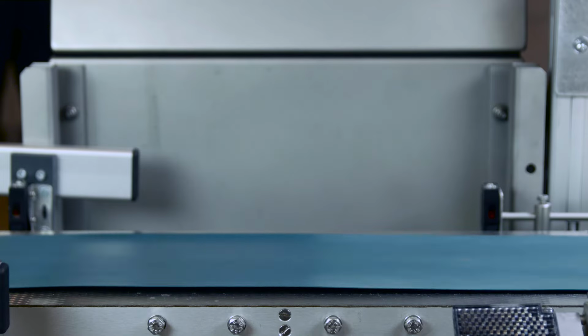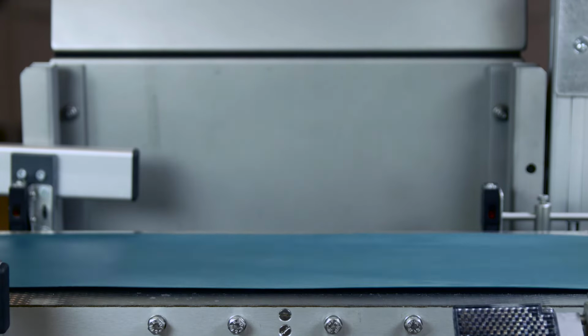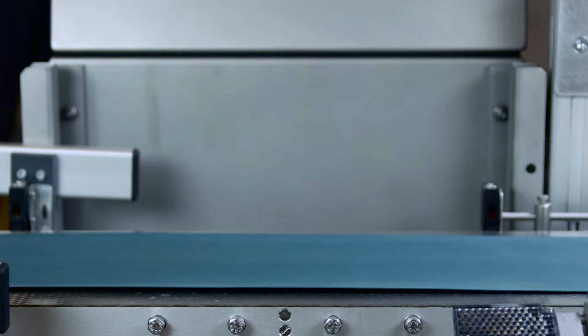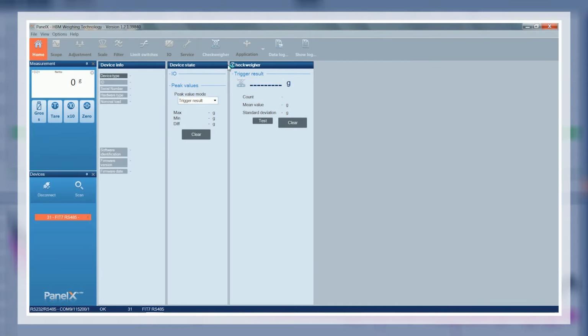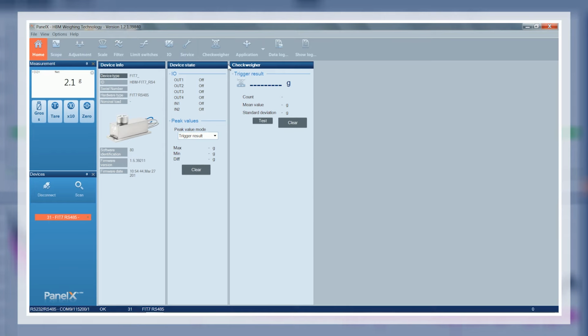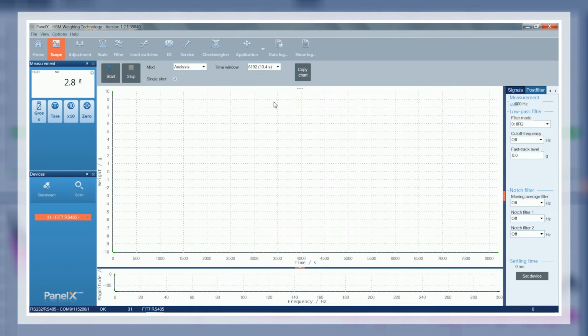First, we do a few test measurements with a single product to be weighed and record the raw signal using the Panel X software. This test data is used for an initial optimization of the electronic processing in Panel X, and the resulting settings will then be forwarded to the sensor array of the FIT-7A. That means that in the future, the processing of the raw data can be done in real time by the FIT-7A electronic system. We will now switch back to the scope view and select the analysis mode.